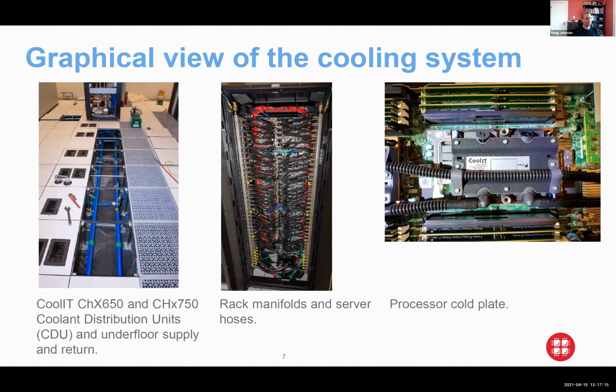To go a little more into the nitty gritty of the diagrams, to expand on Rich's diagrams: we get that condenser water loop run into a CDU, a coolant distribution unit. We've got a secondary loop with a heat exchanger connected to that condenser water loop, and that's in turn circulated into rack manifolds and into the individual servers. You can see what a dense rack looks like.